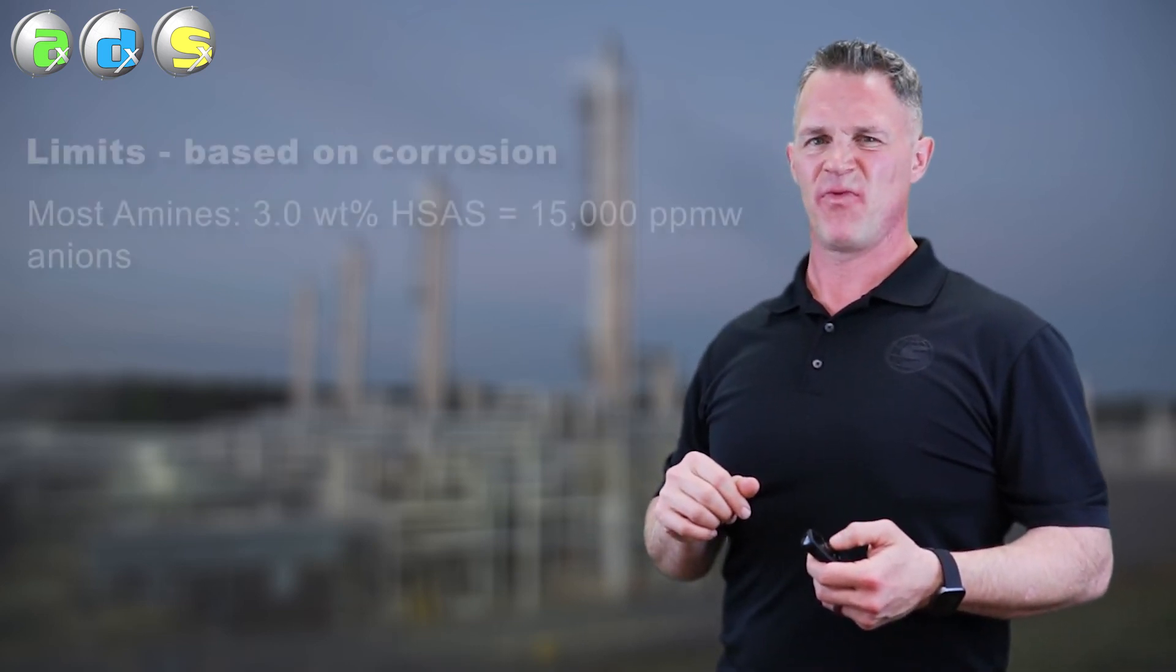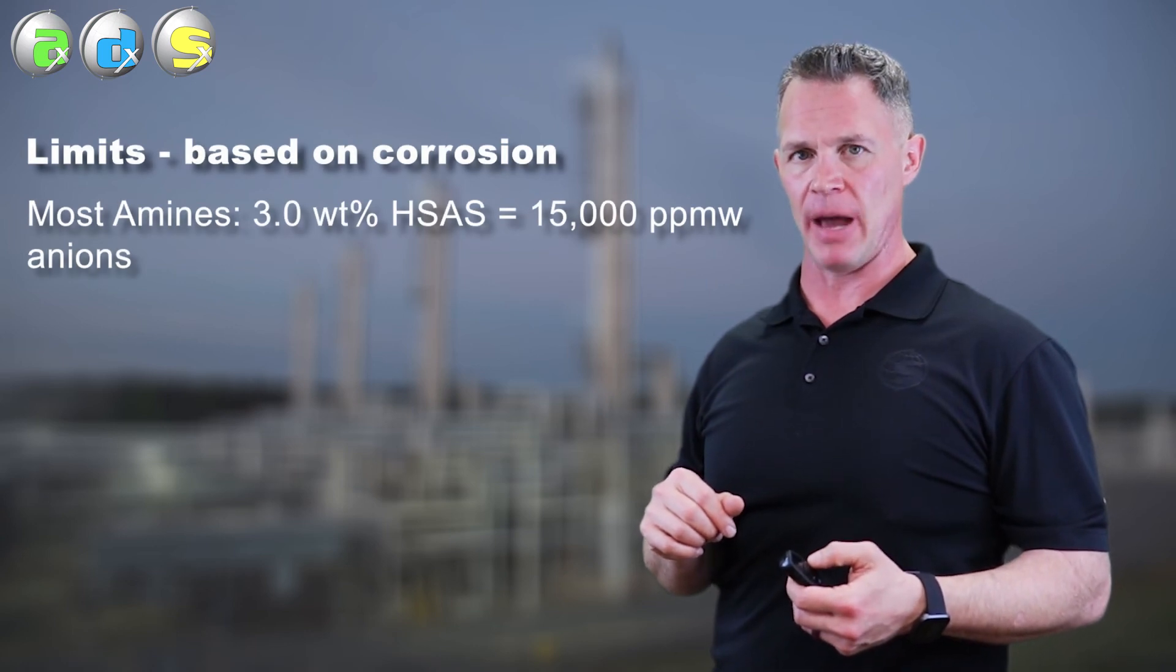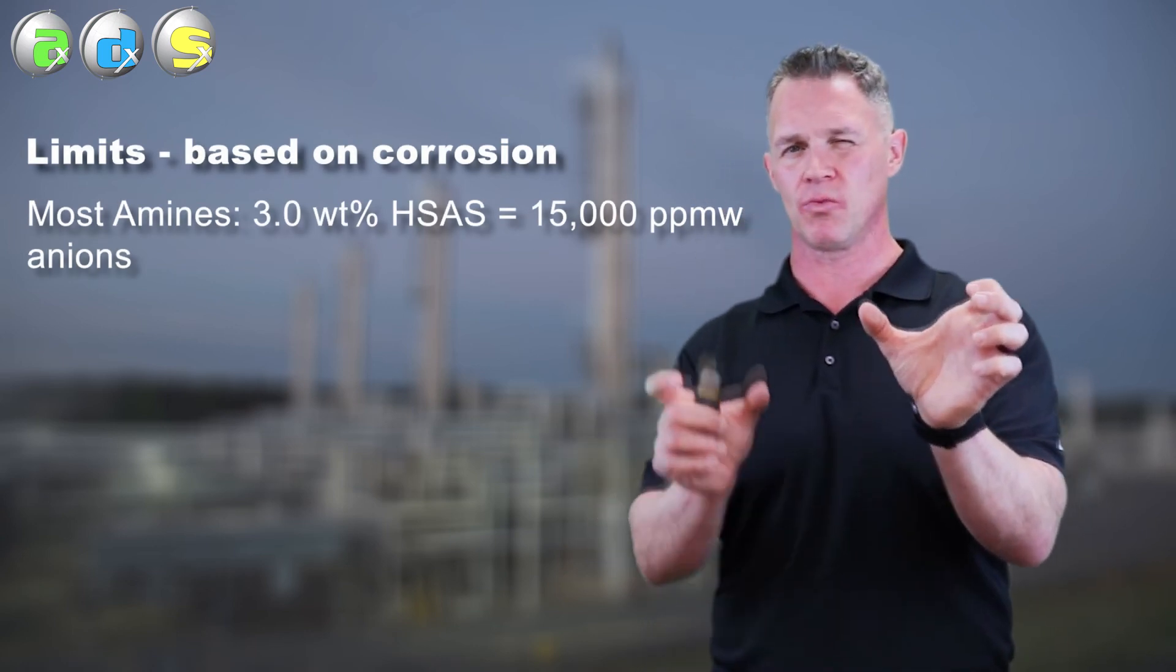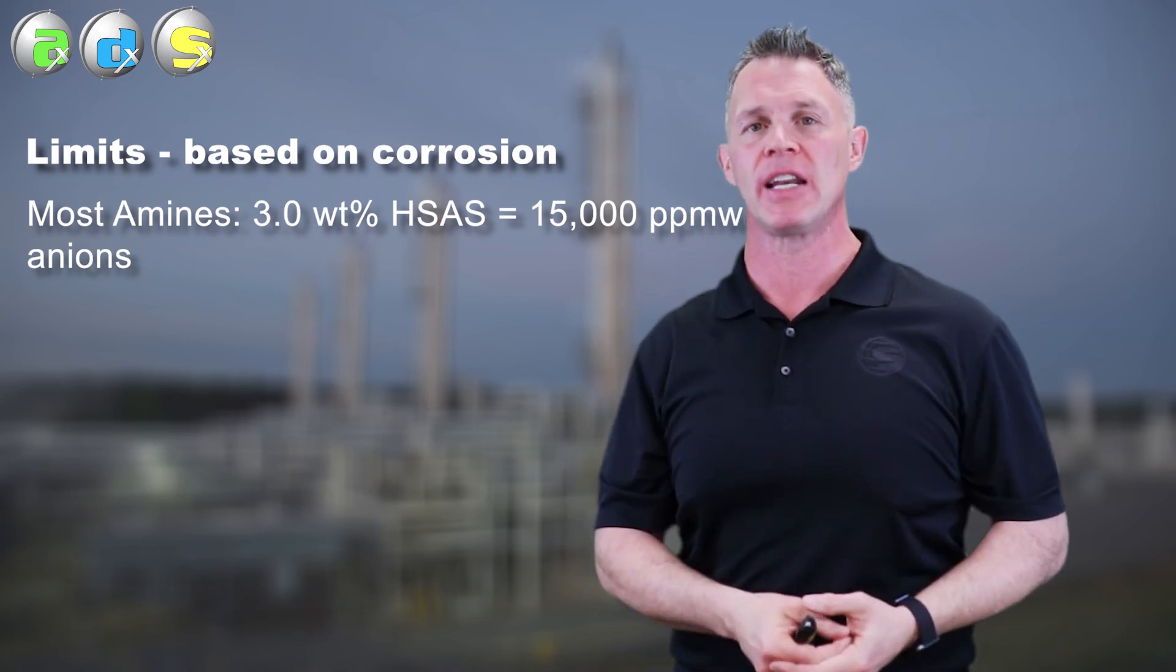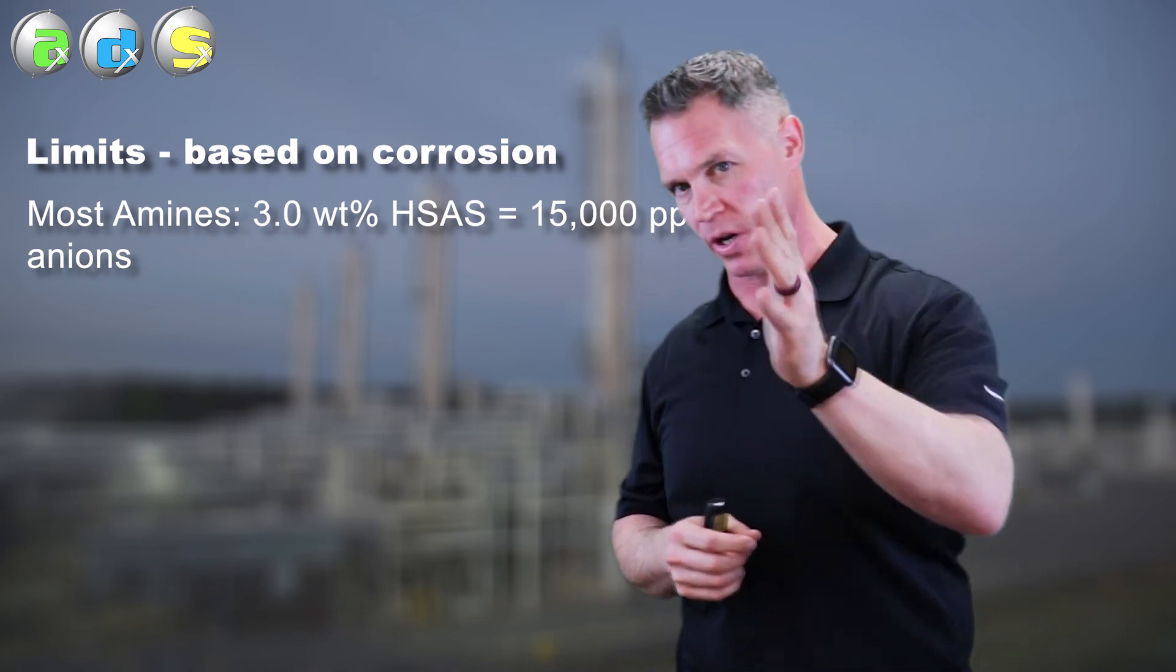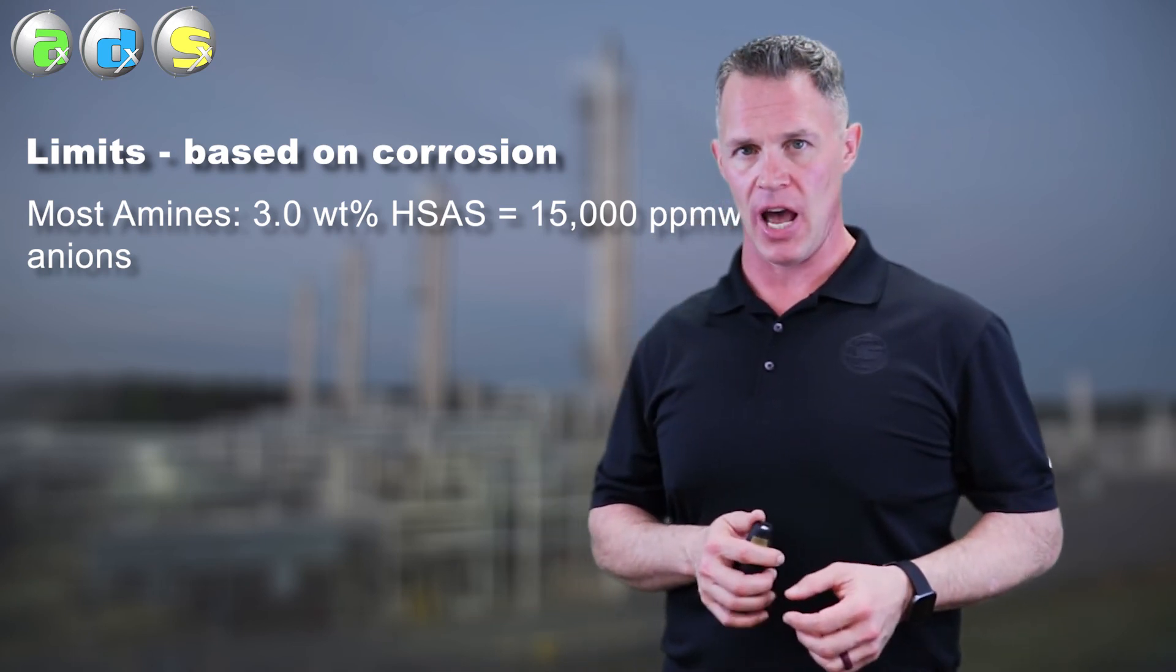You don't want them to exceed about 13,000 to 15,000 ppm. That'd be the maximum. 15,000 ppm acid anions is roughly the equivalent of 3 weight percent heat stable amine salt. And that's where you're crossing the line, that's where you're going to have corrosion.